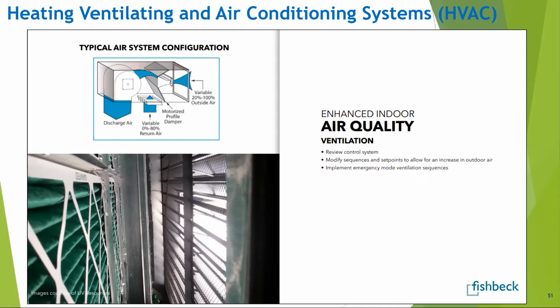And so as part of this effort, they are reviewing our control system, modifying our sequences to allow for increased outside air, and developing this emergency mode or enhanced ventilation sequence for our building automation system, which controls things like that damper you see there in that graphic.